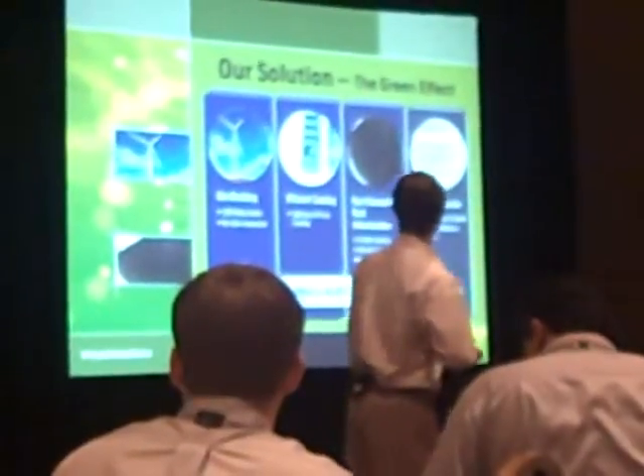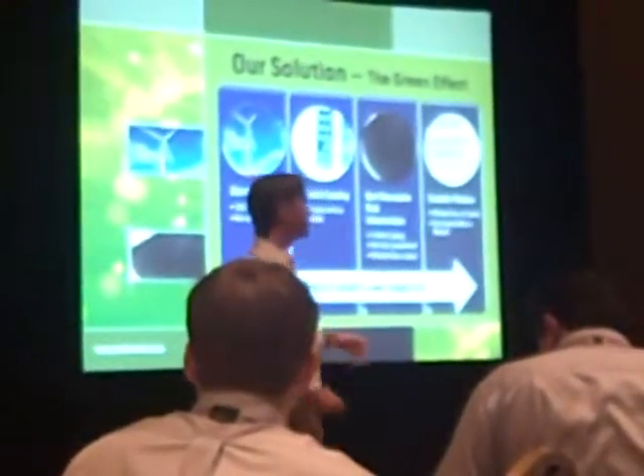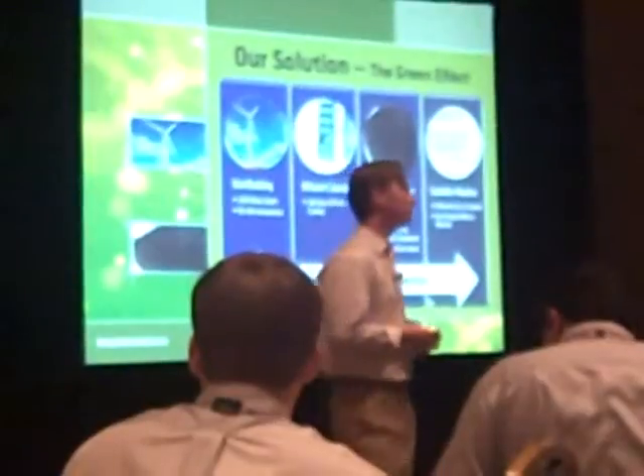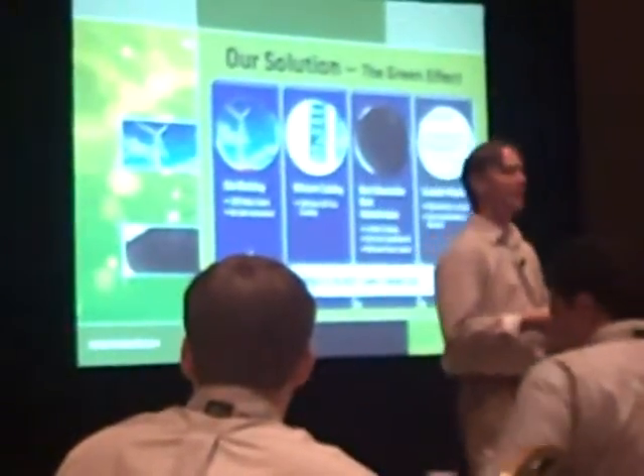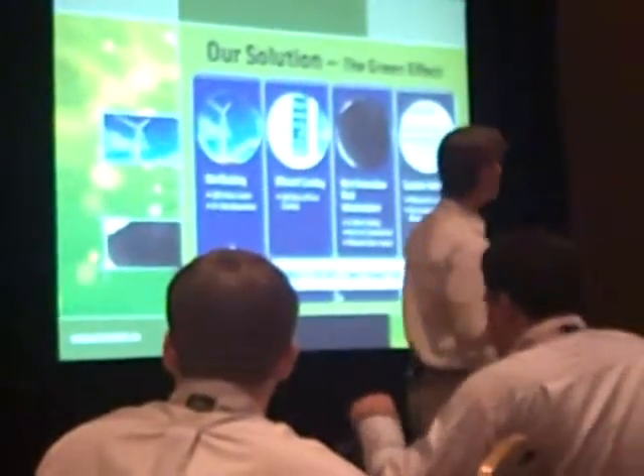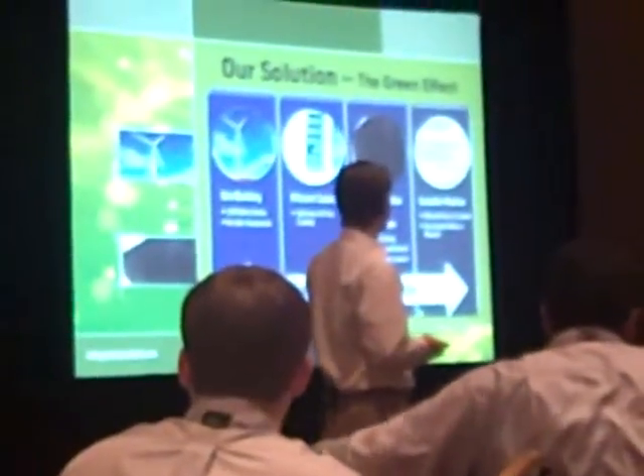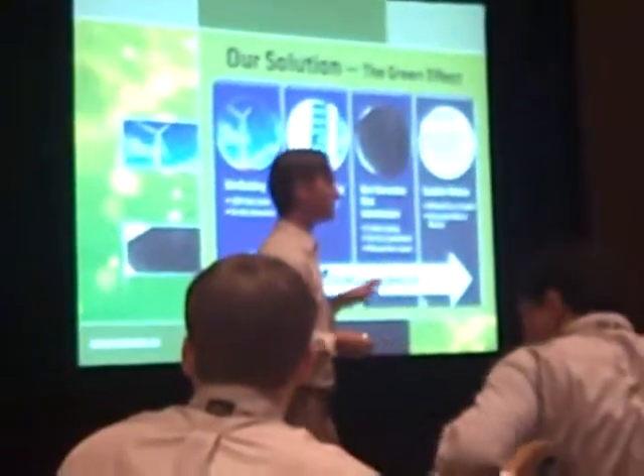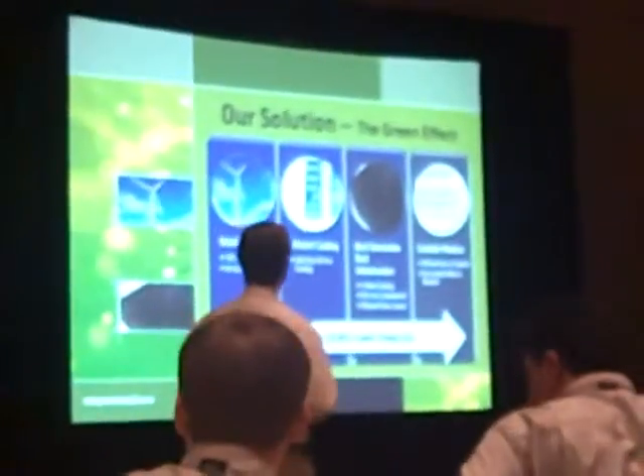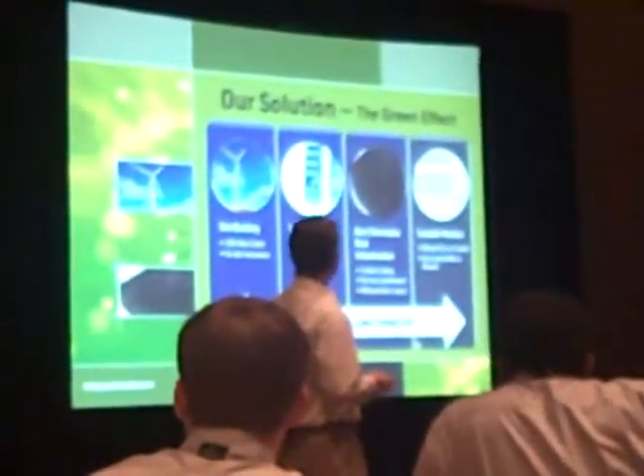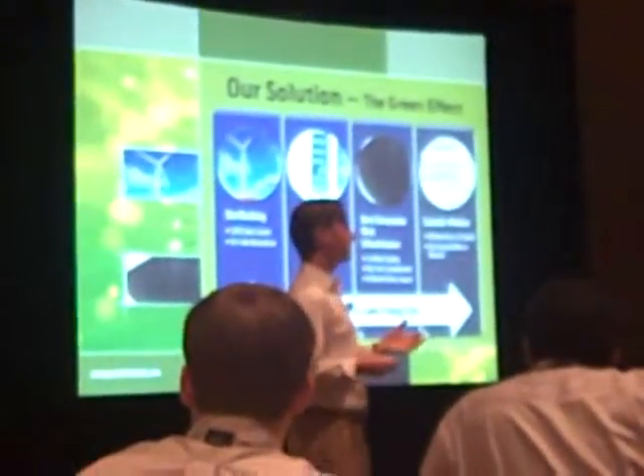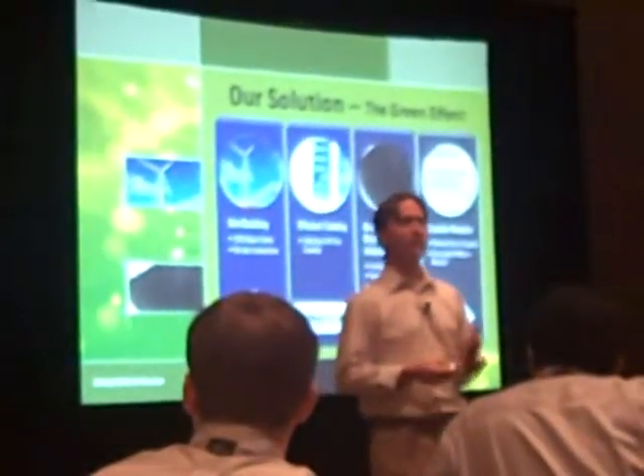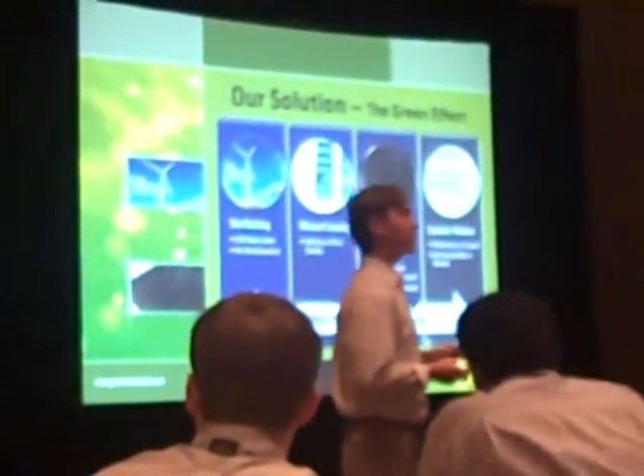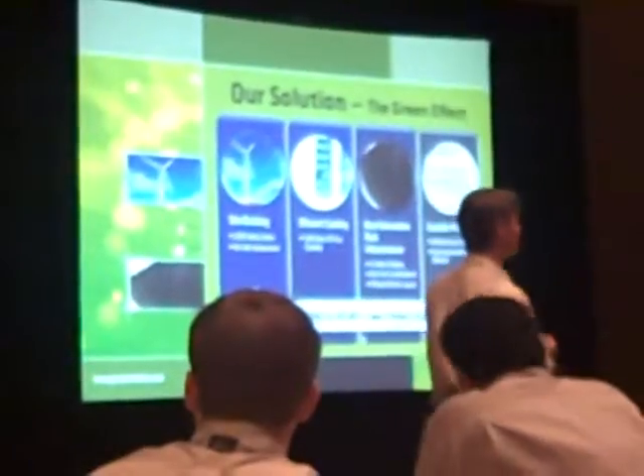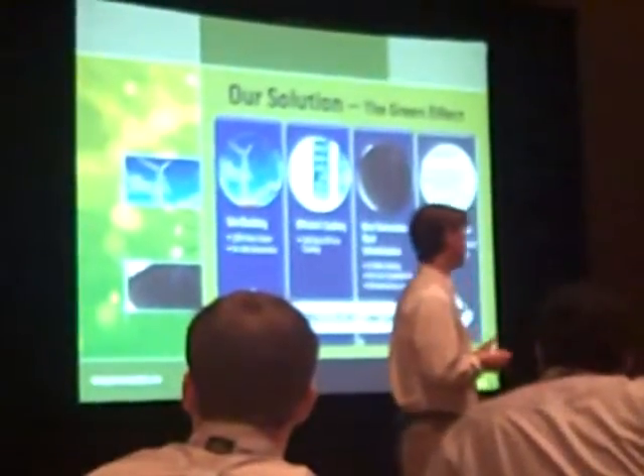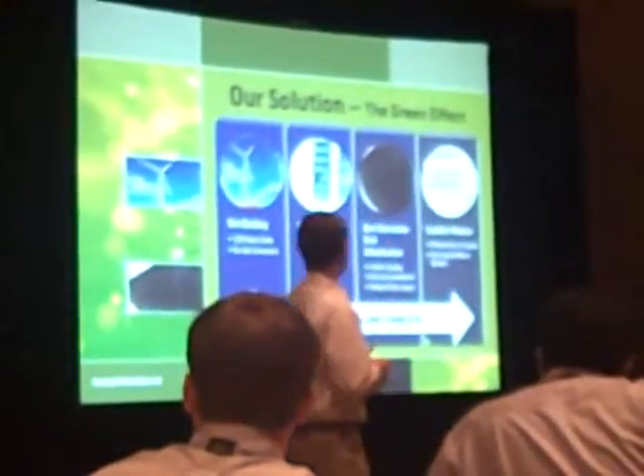So we've been focused at the site level. We are working to become a LEED certified data center facility, and within the next 8 to 12 months we'll have on-site wind generation. Our on-site generation is going to be used to power our cooling infrastructure, which we'll talk about here shortly. Our cooling design allows us, with the ambient air temperatures in Wyoming, to get about 360 to 365 days of free cooling using airside economizers of a specific type.